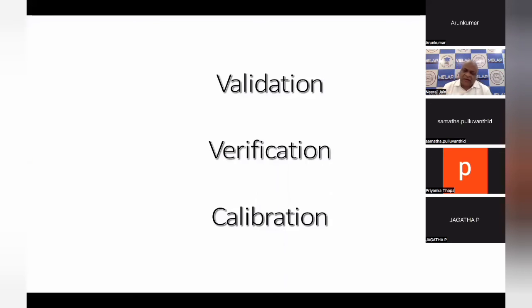Analytical instruments, your analyzers, where you are getting some result. Now, what is the structure of these equipments? They have a light source, light is passing through a solution, then passing through a filter, detected by the optical system, and you are getting some absorbance. Absorbance is proportional to the concentration of analyte in the calibrator.